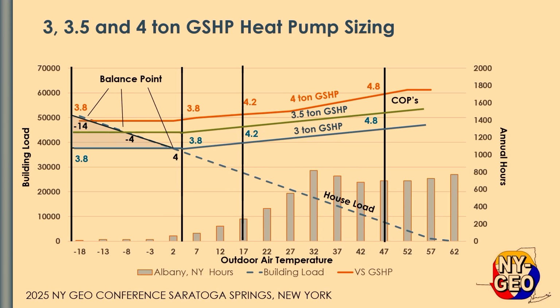You can see the load line of the structure is the same right here. So there's the house load. We've got the Albany, New York hours here, and I've still got the 47, 17, and 5 vertical lines there so you can kind of see where that's at. But I've got the COPs written up here for a ground source heat pump, and this is a variable speed unit. So you've got a COP of 4.8 up here at 47.